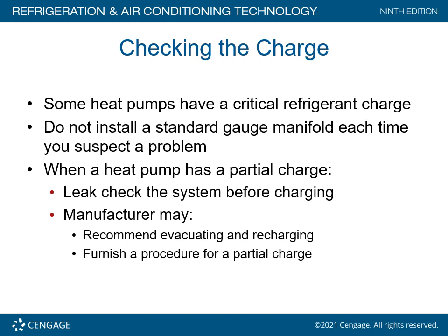I have worked on heat pump systems that have a small leak. They're hard to find, and typically I will notice that there is a problem by looking at the outlet temperature in the supply grill. Let's just say as an example, I operate a heat pump in a four-story condominium complex in Beverly Hills, California. In the heating mode, the design supply temperature should be about 100 degrees, and I'm only reaching 75. Well, that means we've got a problem with the refrigerant charge.